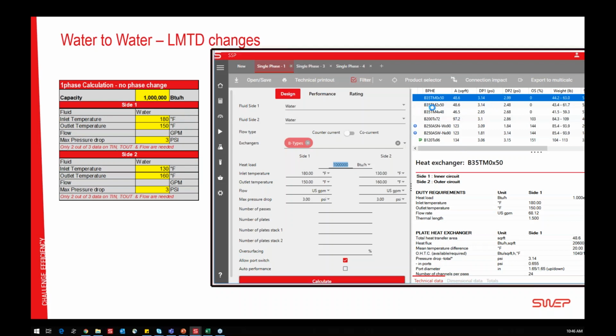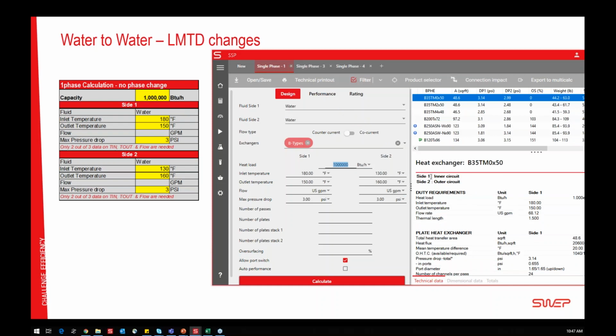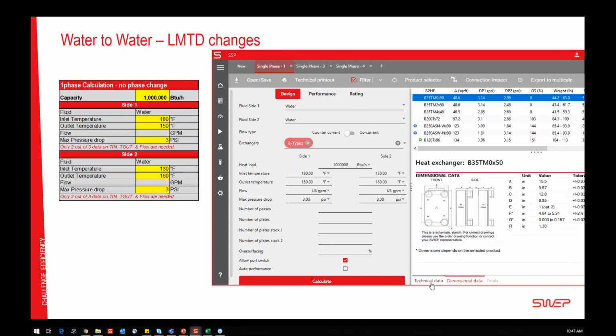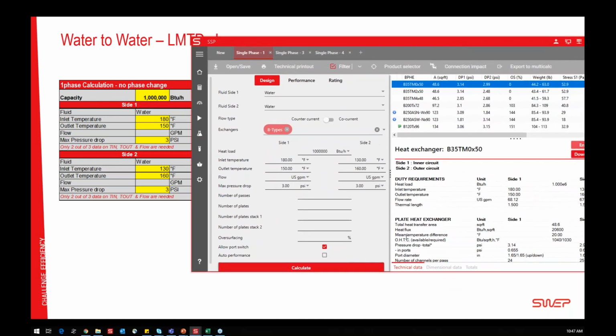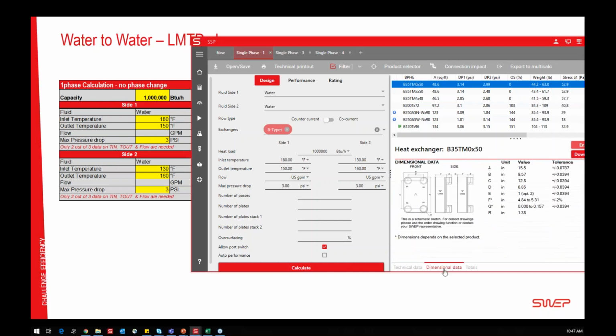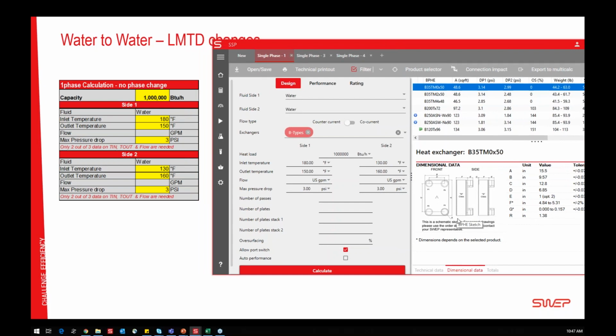What I got then is a B35TM0x50 plates, and now SSP is calculating, so I have to wait anyway. And here we are. Since I can see all the technical data here, including the LMTD, it is 20, which I know. The thermal length is calculated, and the thermal data can be found on this first page. The dimensional data, you can see directly here what is the height and width of the heat exchanger. The A, small written, is the height, about 16 inches. The B is the width, about 10 inches. So it's kind of a short and fat heat exchanger, so to say.